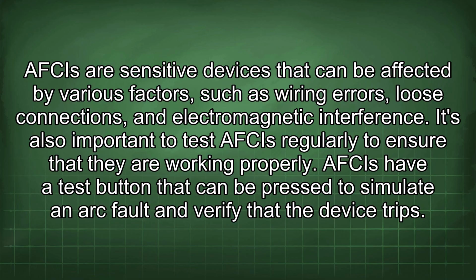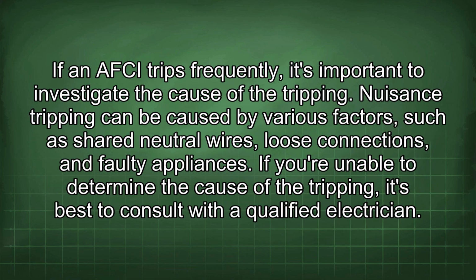It's also important to test AFCIs regularly to ensure that they are working properly. AFCIs have a test button that can be pressed to simulate an arc fault and verify that the device trips. If an AFCI trips frequently, it's important to investigate the cause of the tripping. Nuisance tripping can be caused by various factors such as shared neutral wires, loose connections, and faulty appliances. If you're unable to determine the cause of the tripping, it's best to consult with a qualified electrician.